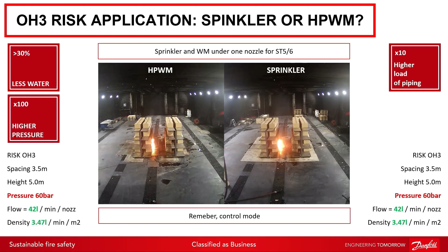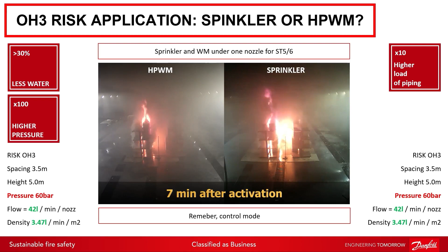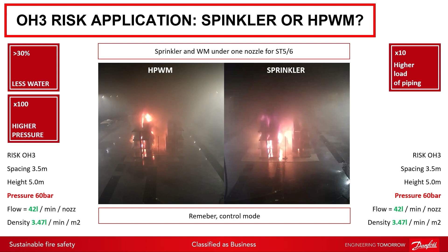And here, you remember at the very first I told you about fire control. Here our task is to control the fire, which means that the fire is not spreading to the next, and therefore we are controlling it, and in fact the fire brigade will come and put out the fire. But you can see the same fire load is in both cases, and you are doing the sprinkler according to the density in the standards, and you could see that the fire expanded. So our high pressure water mist is using 30% less water, 10 times less weight, not only the steel pipe but inside the water. And the pressure, you could see that the pressure in our case is 60 bar. So this is water mist. I think I don't need to tell more about this video.